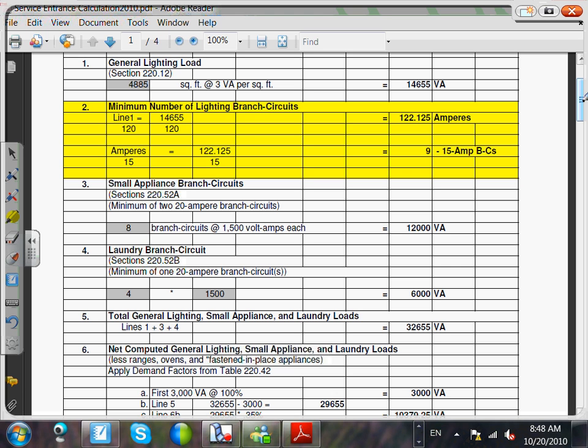for a residential building. This volt amp per square foot covers the following: all lighting and convenient receptacles. Only for residential, this table will cover convenient receptacles. When we use it for commercial later on, receptacles will be done separately. They're done on a separate calculation.